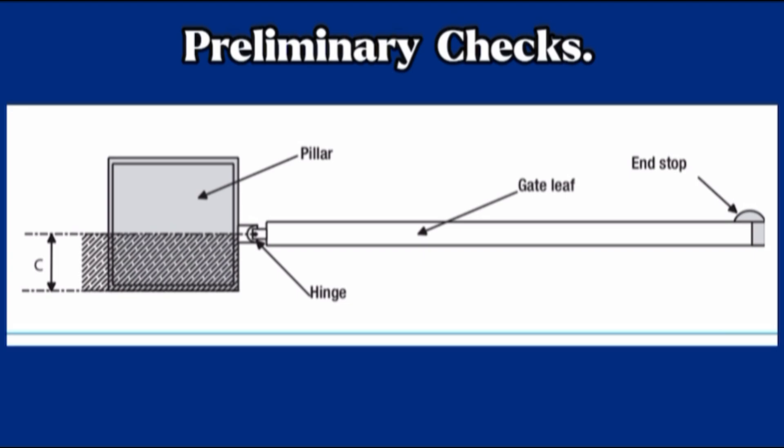There must be a soundly secured to the ground mechanical stop to prevent the gate leaf gear motor from overextending. Any connections inside the case that provide continuance to the protective circuit must be fitted with extra insulation as compared to the other conductive part inside. Make sure you have suitable tubing and conduits for the electrical cables to pass through and be protected against mechanical damage.